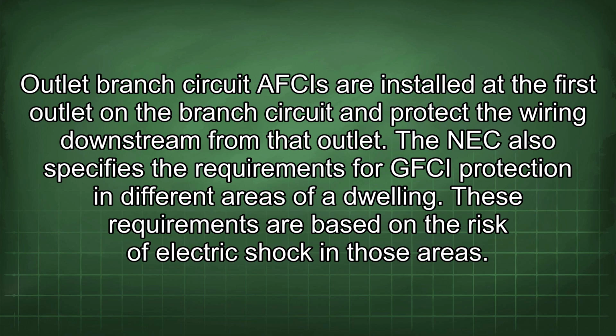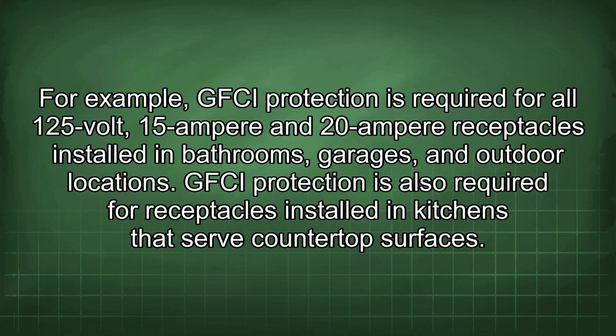These requirements are based on the risk of electric shock in those areas. For example, GFCI protection is required for all 125 volt, 15 ampere and 20 ampere receptacles installed in bathrooms, garages, and outdoor locations. GFCI protection is also required for receptacles installed in kitchens that serve countertop surfaces.